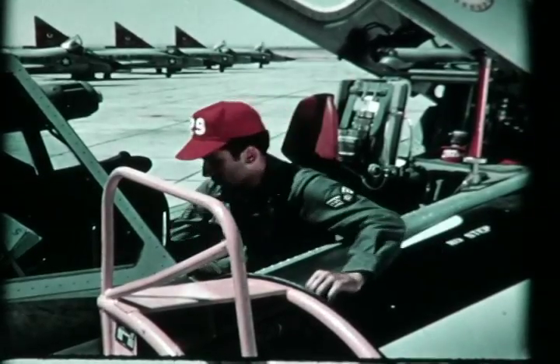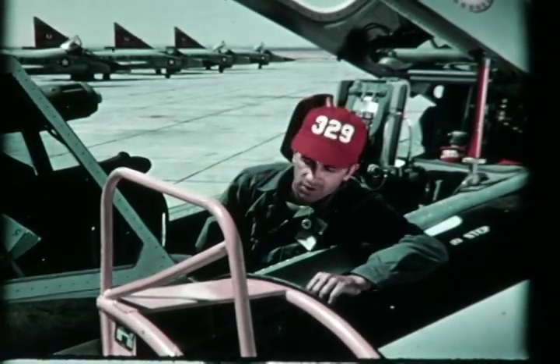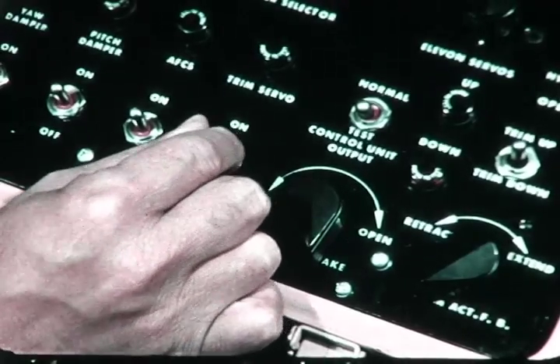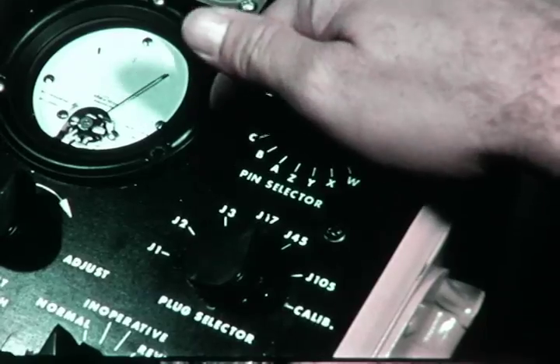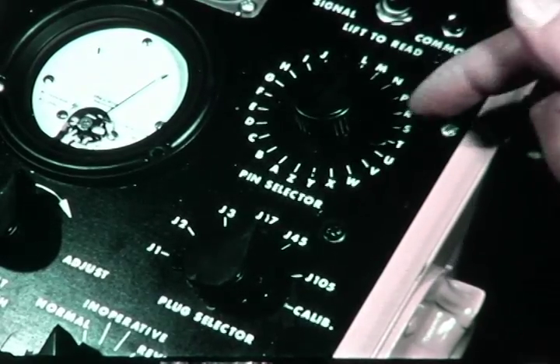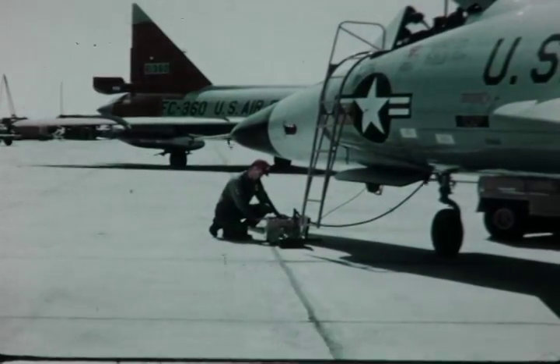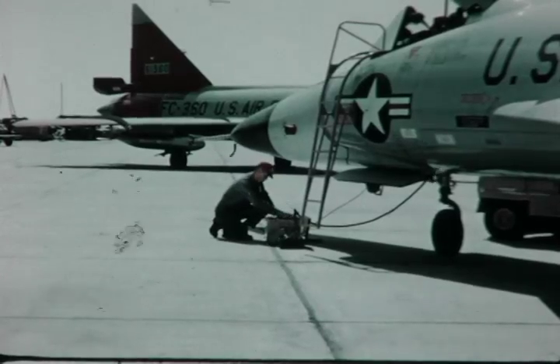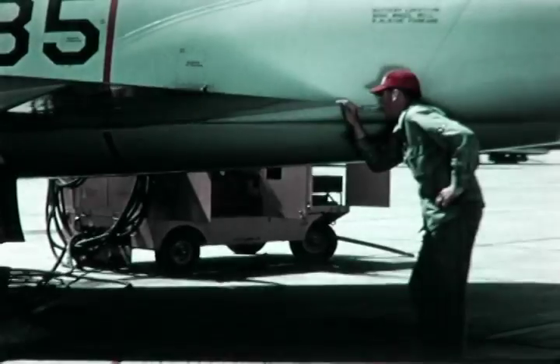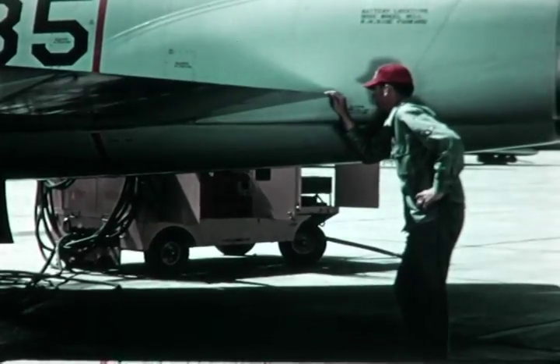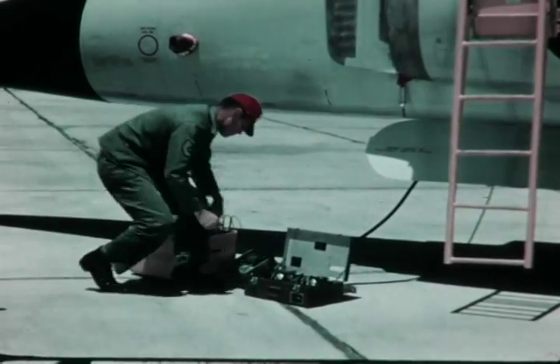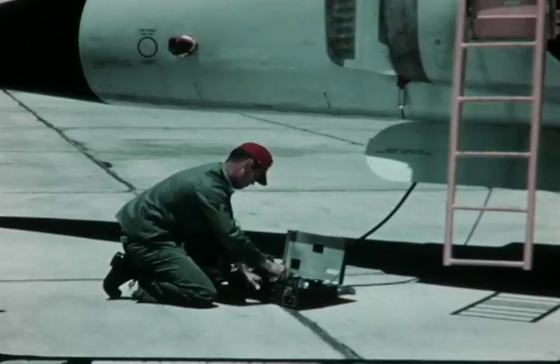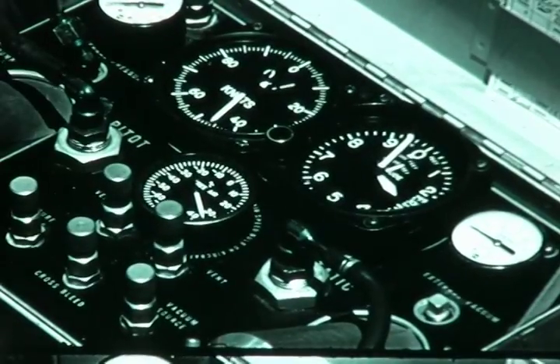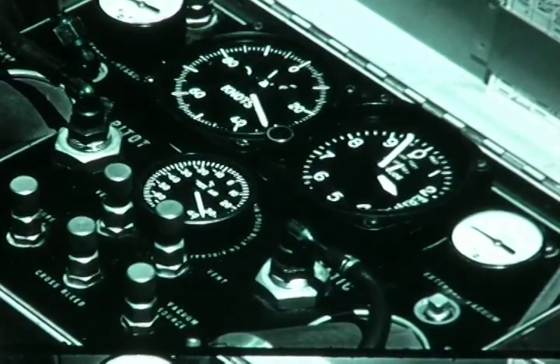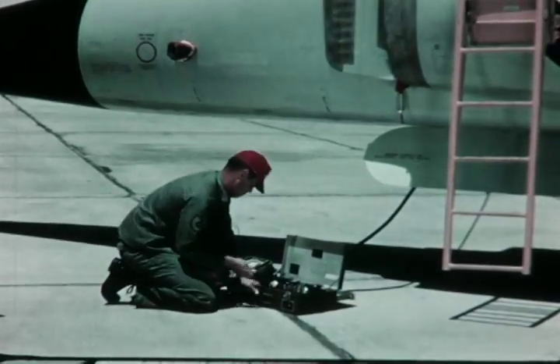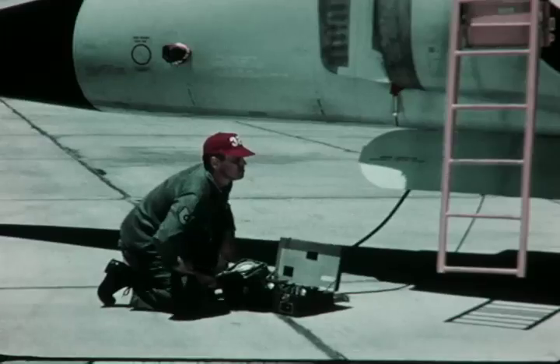Actuate the trim servo switch in the cockpit to the on position. Engage the trim servo switch on the tester. Now on your VTVM, you can read voltages on these pins A through V as called out in your tech order. With the switch in the test position, the up and down lights illuminate when the control unit output up or down relay operates. The elevator trim actuator can be functionally checked by operating it from the tester. As we mentioned before, a pitot-static tester has been connected to the pressure ratio transducer, and when 1.6 times barometric air pressure is applied to the controller, the elevons should respond by moving a maximum of 8.5 degrees up position.